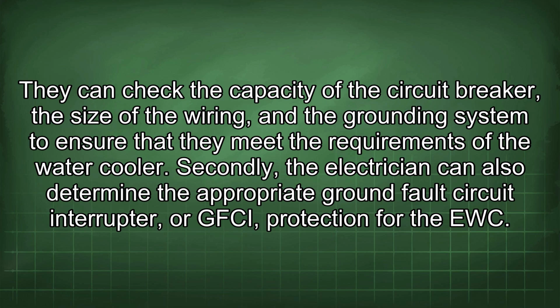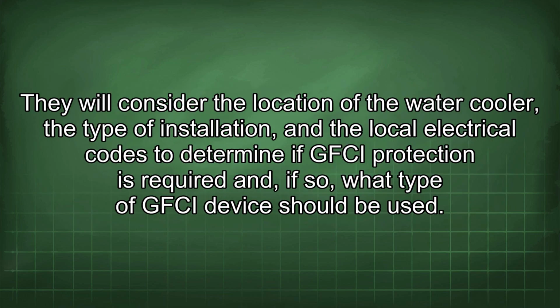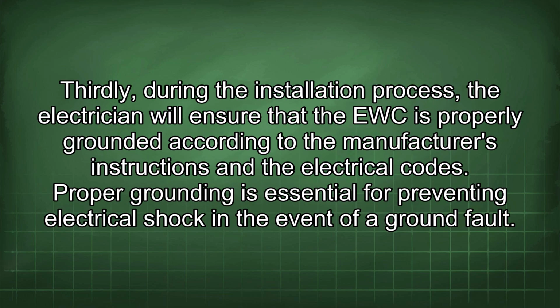Secondly, the electrician can also determine the appropriate ground fault circuit interrupter, or GFCI, protection for the EWC. They will consider the location of the water cooler, the type of installation, and the local electrical codes to determine if GFCI protection is required and, if so, what type of GFCI device should be used. Thirdly, during the installation process, the electrician will ensure that the EWC is properly grounded according to the manufacturer's instructions and the electrical codes. Proper grounding is essential for preventing electrical shock in the event of a ground fault.